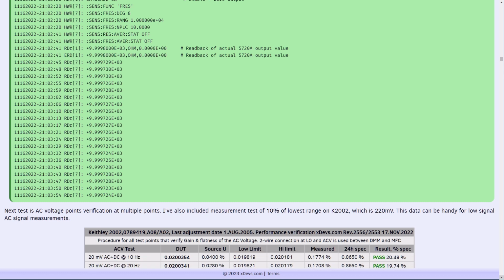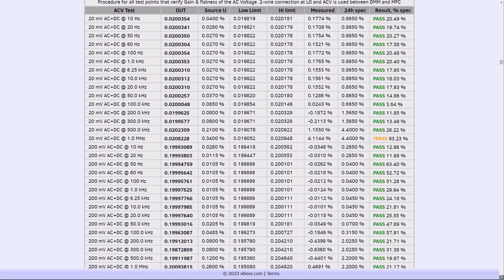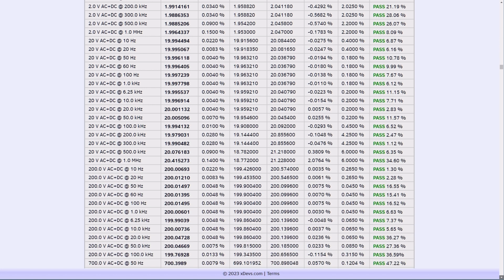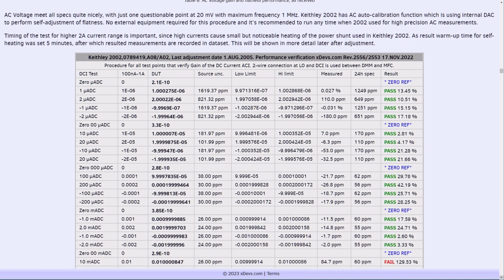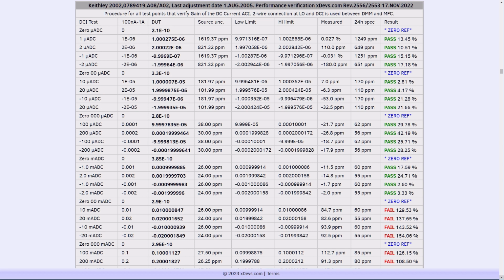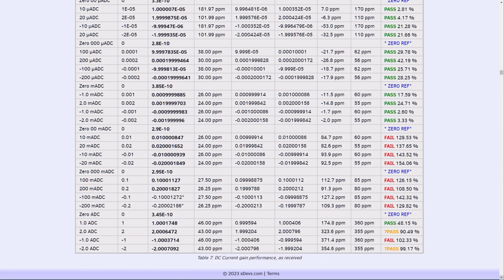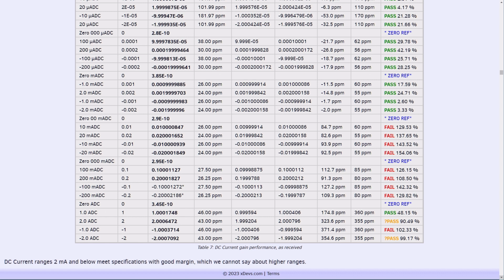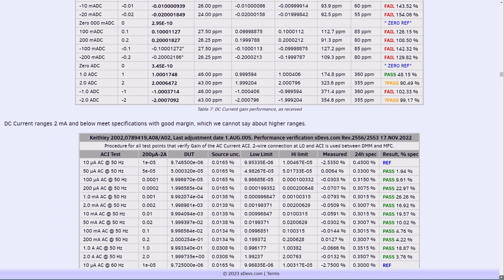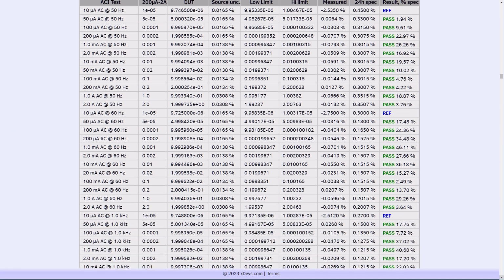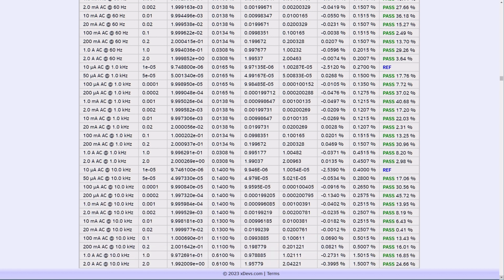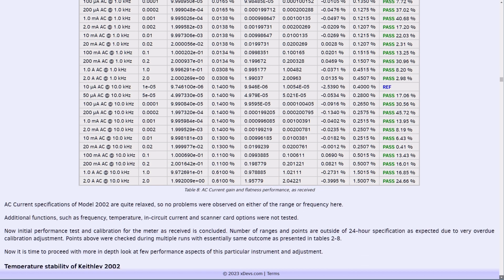Next test is AC voltage, and there were no surprises there. Everything passed with wide tolerances, so no problems. Next is DC current, and here we have 20 milliamp and 200 milliamp failing specs again, as well as 2 amp barely meeting the 24-hour spec. So the next is AC current, and AC current is pretty wide in tolerance, so no problems to pass all the ranges and specs. At this point, we completed initial calibration of DMM for as received condition.